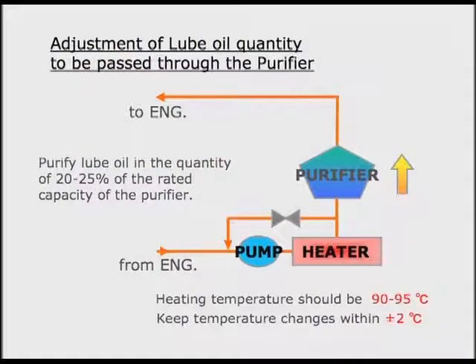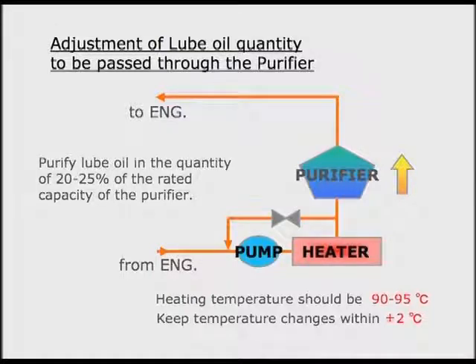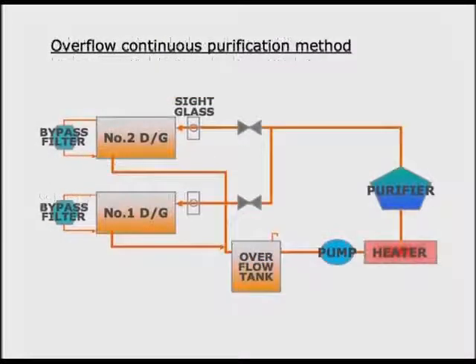Conduct the cleaning treatment with the feeding oil quantity covering 20 to 25 percent of the rated capacity of the purifier. Set the heating temperature at 90 to 95 degrees centigrade and keep the temperature variation within plus or minus two degrees.